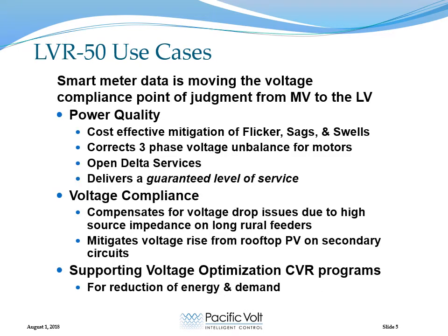In general, the value of this technology is to mitigate voltage problems, either high or low, which are caused by the impedance of the circuit. Typically, the use cases fall into three categories: power quality, voltage compliance, and supplemental support of voltage optimization or CVR programs. It's important to note that smart meter data is moving the voltage compliance point of judgment from the medium voltage substation to the low voltage meter.